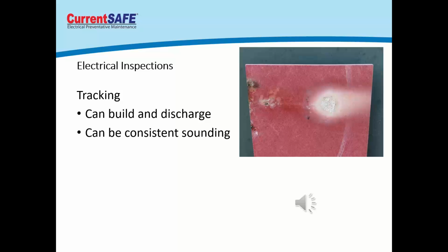We can listen again if you want to any of these sounds, but the more you listen to them, the more you get familiar with them. There's not a lot of temperature difference that we can detect with the ultrasonic probe. Because this is the early warning sign of a problem in a condition in the distribution equipment, it's not really enough of an issue yet for our infrared technology to always pick it up. So just because we can hear it doesn't mean we can see it, which is another great reason to use the ultrasonic probe.